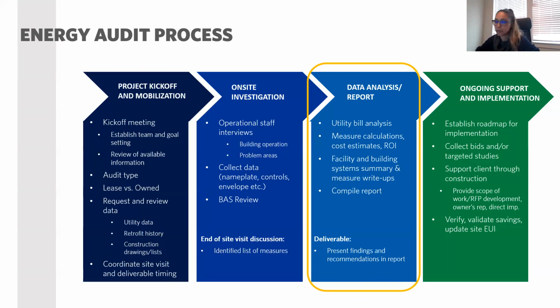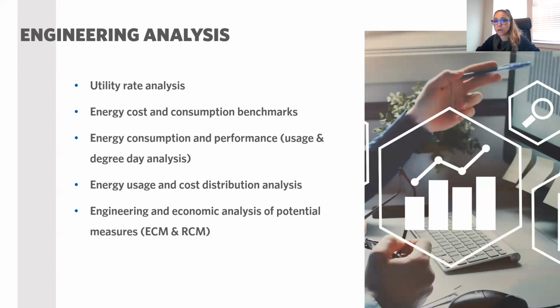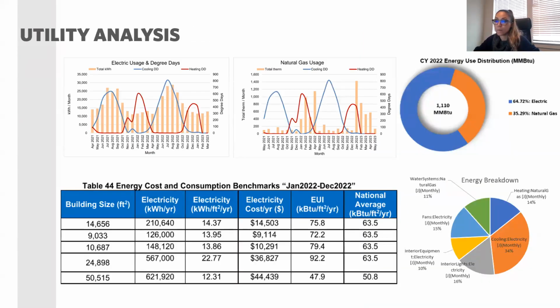The next is the analysis and reporting phase, where we spend most of our time. We start with the utility rate analysis, and then get into energy cost and consumption benchmarking, degree day analysis, energy use distribution analysis, cost distribution analysis, and the actual calculations of the ECMs and RCMs. We first analyze the utility data, which I mentioned earlier. We require at least 2 to 3 years to account for the seasonal variations and patterns of energy use, and we identify anomalies by looking at this degree day graph.